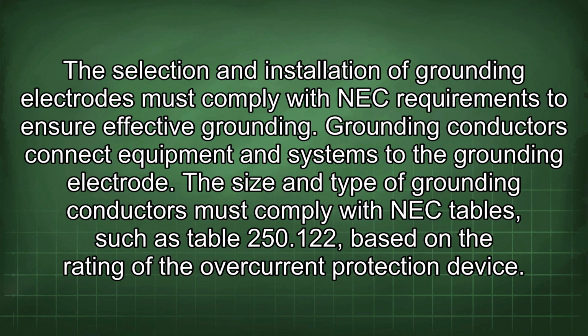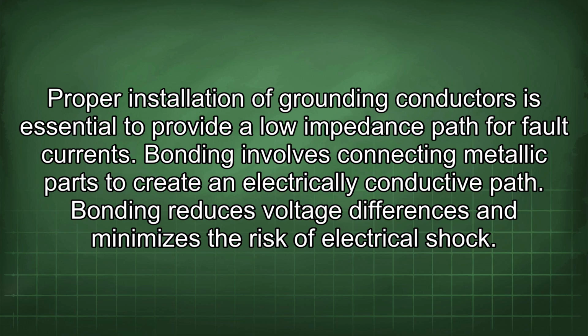Grounding conductors connect equipment and systems to the grounding electrode. The size and type of grounding conductors must comply with NEC tables, such as Table 250.122, based on the rating of the overcurrent protection device. Proper installation of grounding conductors is essential to provide a low impedance path for fault currents.